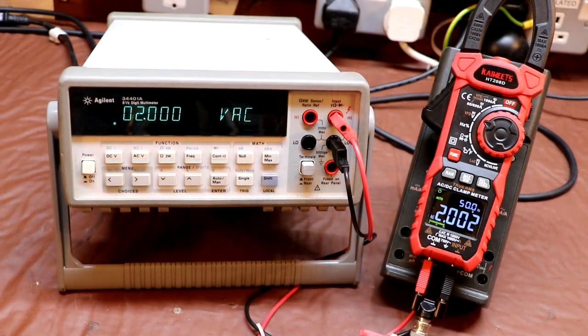I've been having a look at the specification for the KAIWEETS meter, and I don't see that it specifies the bandwidth of the AC volts range. Now for typical domestic and industrial installations, I would expect the frequency to be specified at probably 50 or 60 Hz, but because this meter is designed to work with variable frequency drives, I would expect the frequency range to extend from that to maybe as low as 10 Hz and up to 200 Hz.